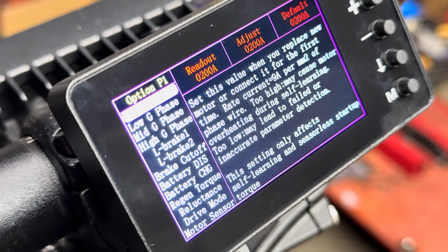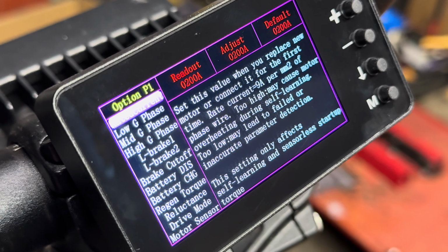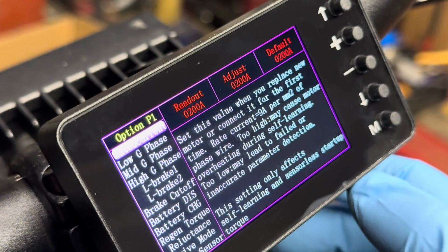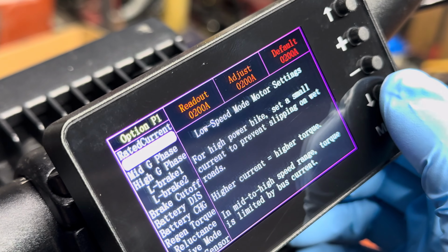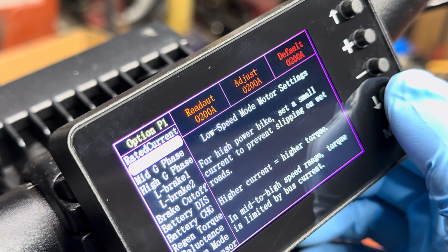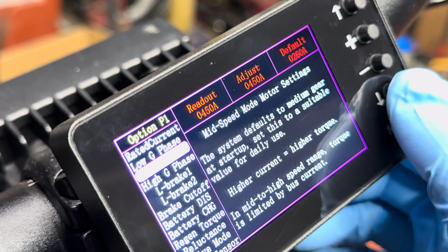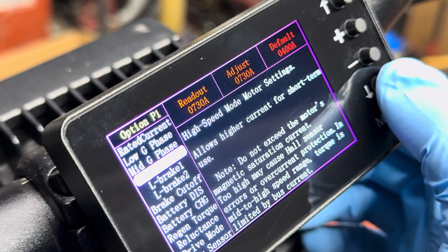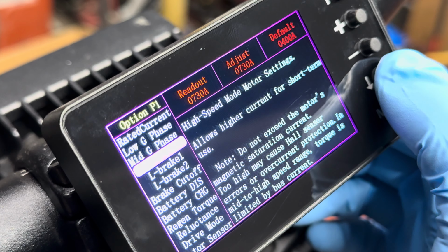Let me see if I can make it easier to read. Rated current, keep it 200 amps. Low G phase I have set to 200 amps. This is your low mode. Your medium power mode, 450 amps. Your high power mode, 730 amps.